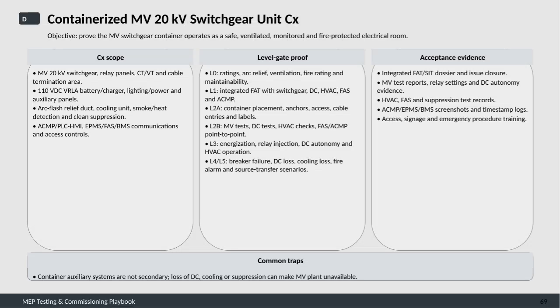This slide covers the testing and commissioning of a containerized 20 kV medium voltage switchgear unit. The main objective here is to ensure that the switchgear container functions as a safe, well-ventilated, monitored, and fire-protected electrical room. Starting with the scope, it includes the medium voltage switchgear itself, relay panels, current and voltage transformers, and the cable termination area. We also focus on the 110 VDC VRLA battery and charger, lighting, power, and auxiliary panels.